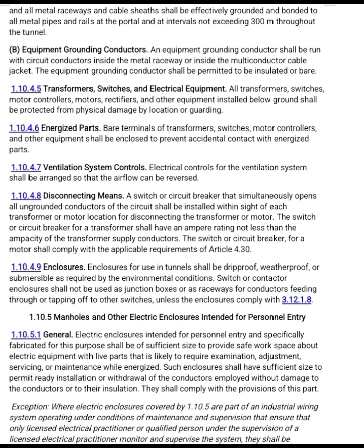1.10.5.1 General. Electrical enclosures intended for personnel entry and specifically fabricated for this purpose shall be of sufficient size to provide safe work space about electrical equipment with live parts that is likely to require examination, adjustment, servicing, or maintenance while energized. Such enclosures shall have sufficient size to permit ready installation or withdrawal of the conductors employed without damage to conductors or to their installation. They shall comply with the provisions of this part.